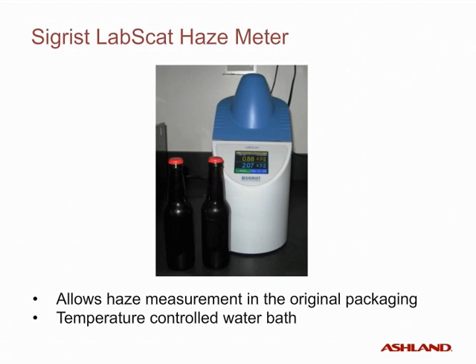Our Sigrist LabScat haze meter allows measurement of haze in the original packaging — bottles do not have to be opened to make the measurement. This allows cycling of the beer from hot to cold to perform accelerated aging without exposing the beer to the environment. The color of the bottle has no impact on the haze measurement. This haze meter has temperature-controlled capacity within the water bath to hold the samples at the desired temperature while the measurement is being made, generally at 0 degrees Celsius.